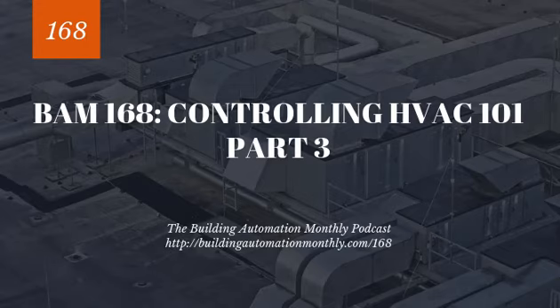And recall that I said in previous episodes design days are days in which you are going to be at or exceeding the capacity of the designed system. So these aren't going to dramatically affect the air-cooled chiller efficiency on normal days, but on these design days, they can have a large effect.